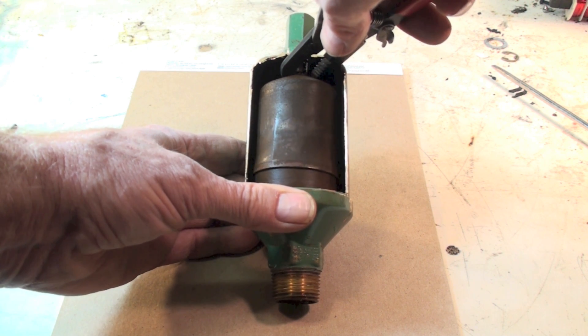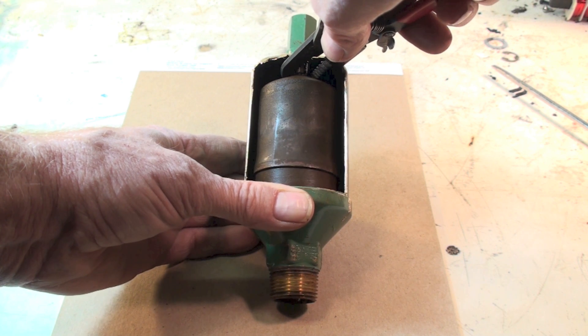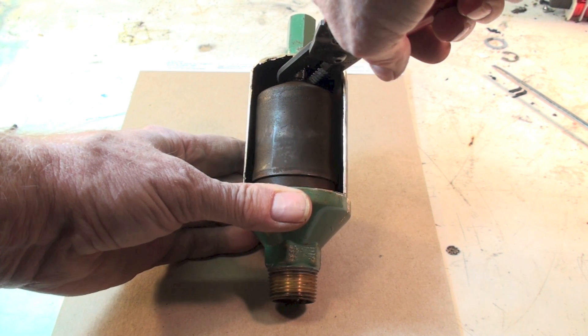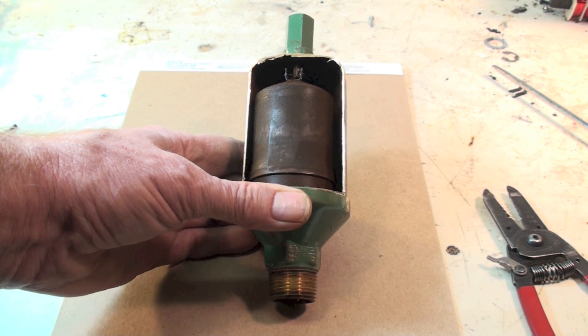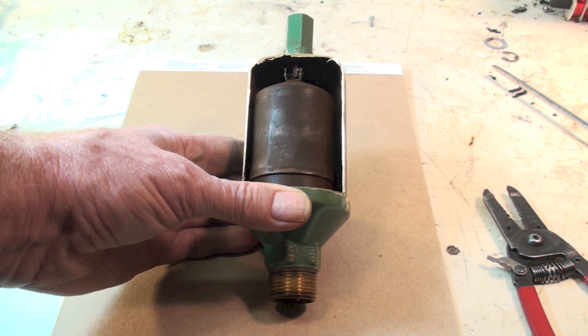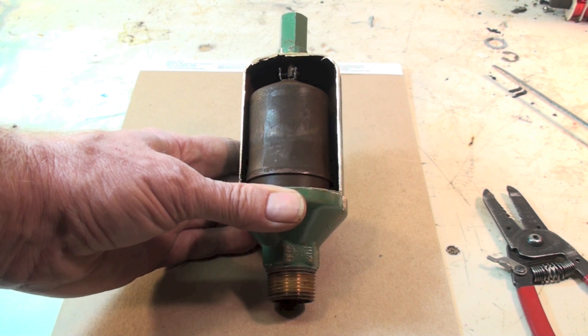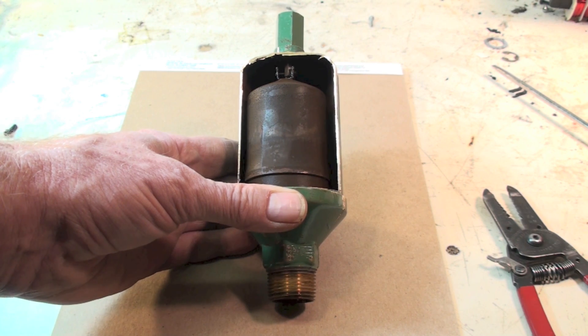If we get air bubbles in there, then the water level is going to drop because the air displaces it, and then this float is going to come down. When it comes down, this valve up here opens up until there's no more air in it, and then it closes again — very, very simple, very effective device.